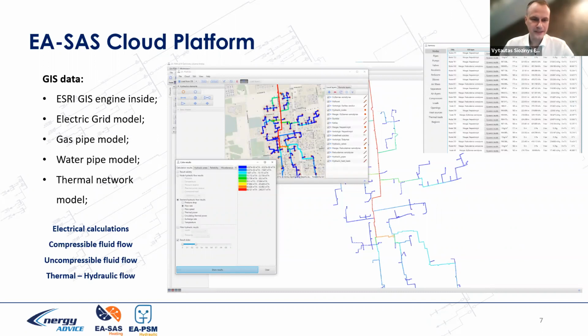Our cloud solution also has GIS integration with the EA-PSM desktop software, and our GIS has ESRI technology inside. We have an ESRI GIS engine, electric grid data models, gas pipe models, water pipe models, and thermal network models. So in fact, we are capable of performing any kind of electrical calculations, compressible fluid flow, incompressible fluid flow, and thermal hydraulic flow. Coming back to today's discussion on thermal hydraulic flow, we run it in real time without human intervention on the server side. These thermal hydraulic flow calculations are done through the optimization of the supply temperature, in other words, reduction of heat losses in the heating network.